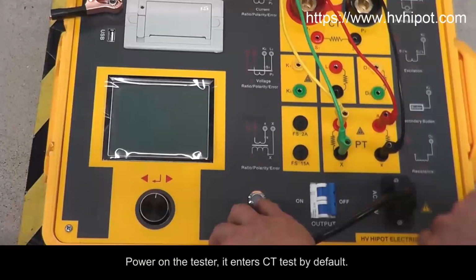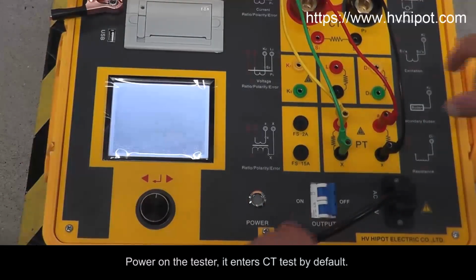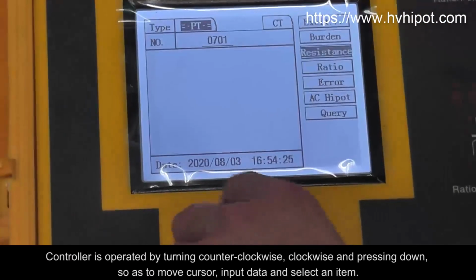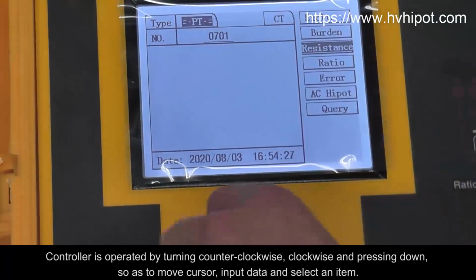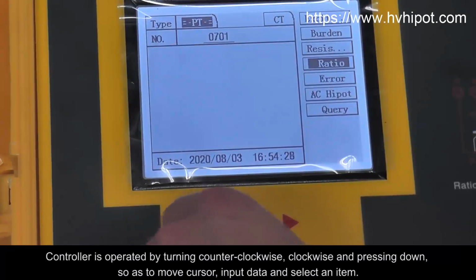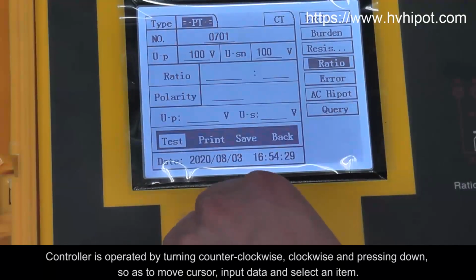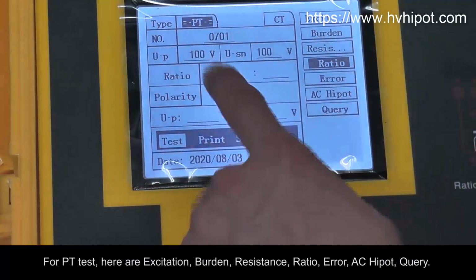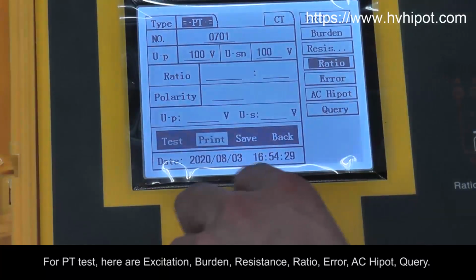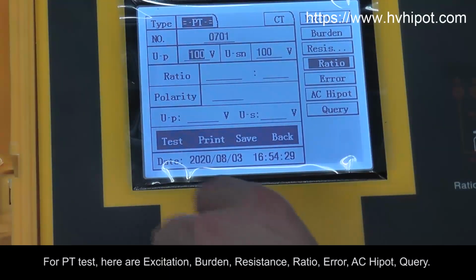Power on the tester, it enters CT test by default. Controller is operated by turning counter-clockwise, clockwise and pressing down, so as to move cursor, input data and select an item. For PT test, here are excitation, burden, resistance, ratio, error, AC hipot query.